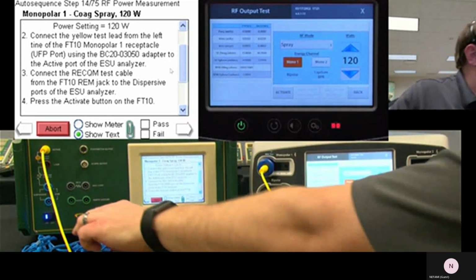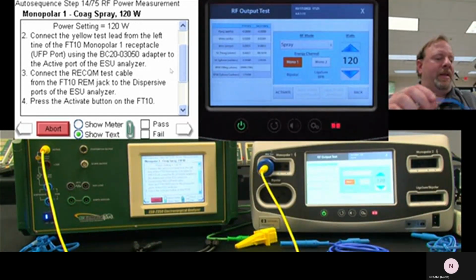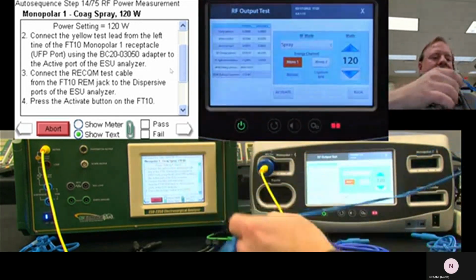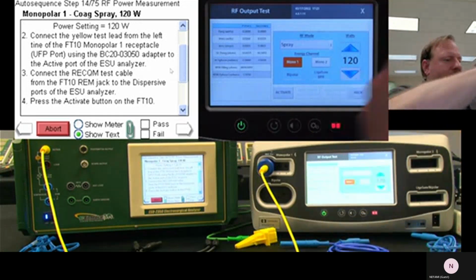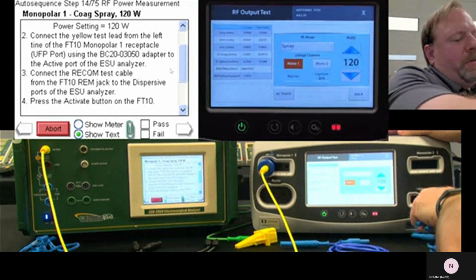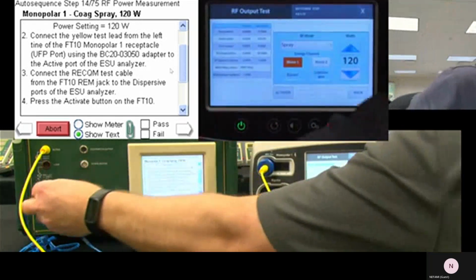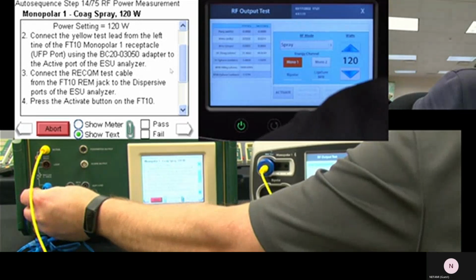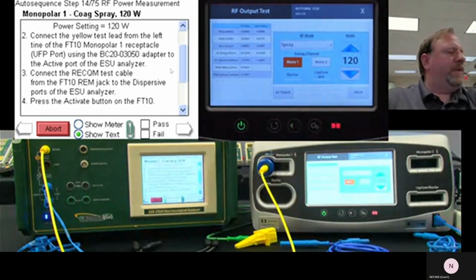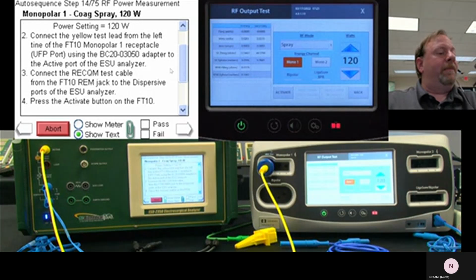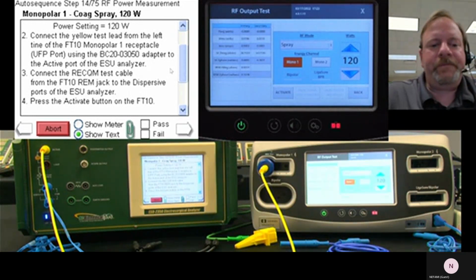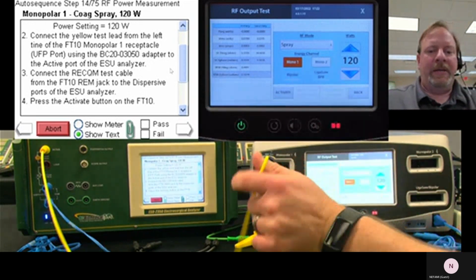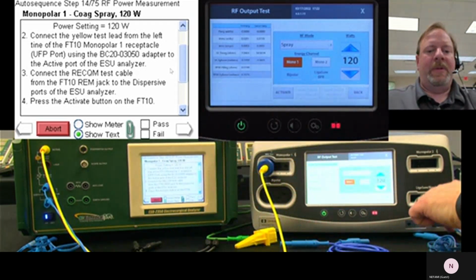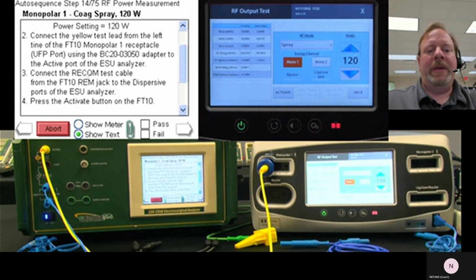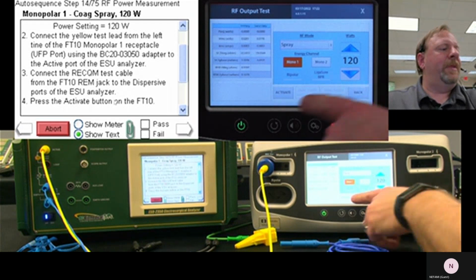And then we're going to take our dispersive cable, and in this case, it's probably going to yell at me because I'm going to use the one without the pin, but the FT10 requires REM. And that's why we go into this special test mode, because that allows us to bypass it. Now in clinical mode from the normal main screen, it'll yell at you if you try and use this cable and if you don't have a good pin. So we've got our connections. It said active to the leftmost tine, connect the REM cable, and now it's telling me activate the FT10. So that's this button here.